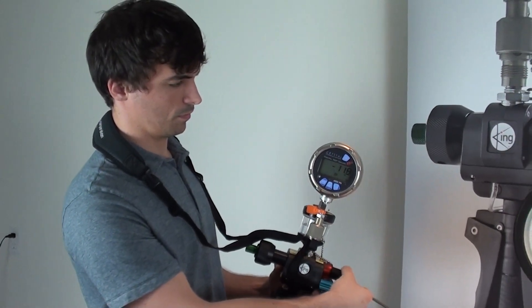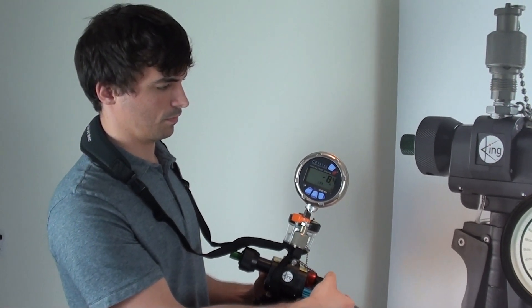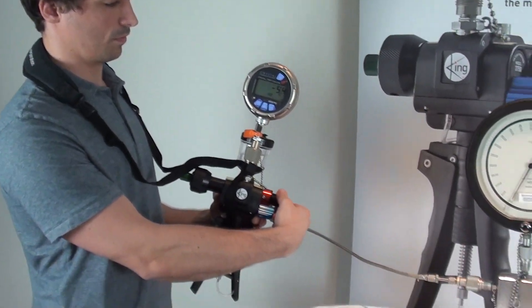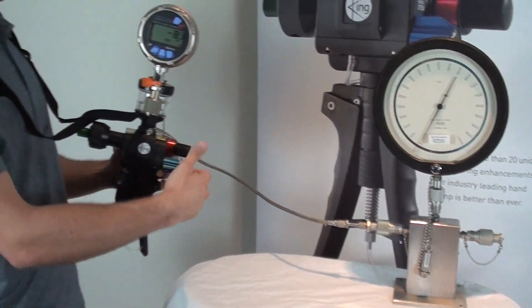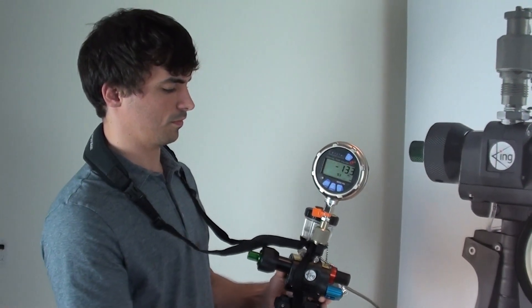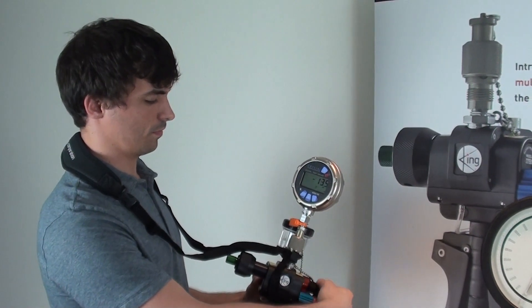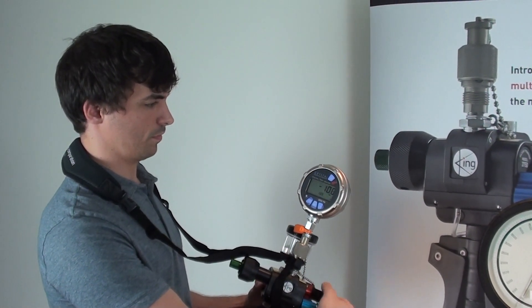So once we've generated a pretty sufficient vacuum, we're going to open up the vent valve. And what this will do is draw water into our system. The reason why we're drawing water into the system is so that we don't get issues with compression of any air that's in the system when we generate a high pressure.